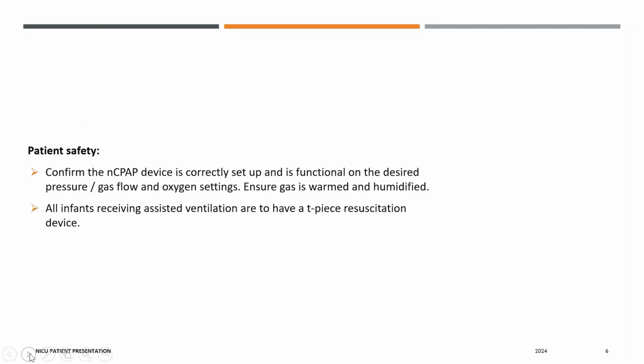Nursing considerations for patient safety. First of all, we should confirm the CPAP device is correctly set up and is functional at the desired pressure, gas flow, and oxygen settings. Ensure gas is warmed and humidified. Then all infants receiving assisted ventilation are to have a T-piece resuscitation device. So before the admission of the baby to the unit, to the bed assigned for the baby, we should make sure that CPAP is ready, and also the T-piece resuscitation device should be set. PEEP and oxygen flow and the air and oxygen blender, everything should be kept ready before the admission.